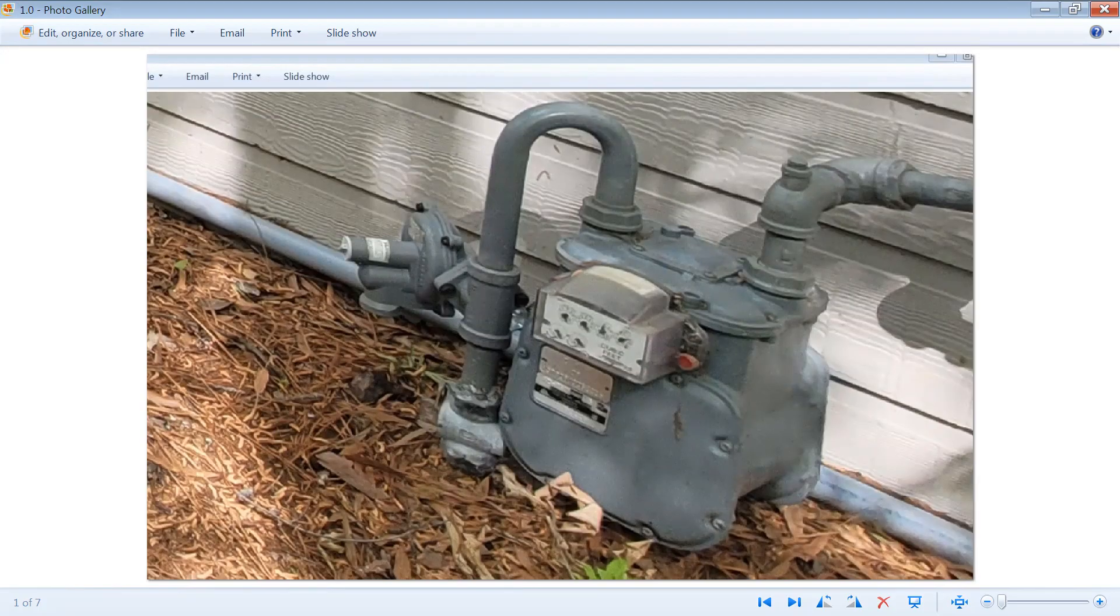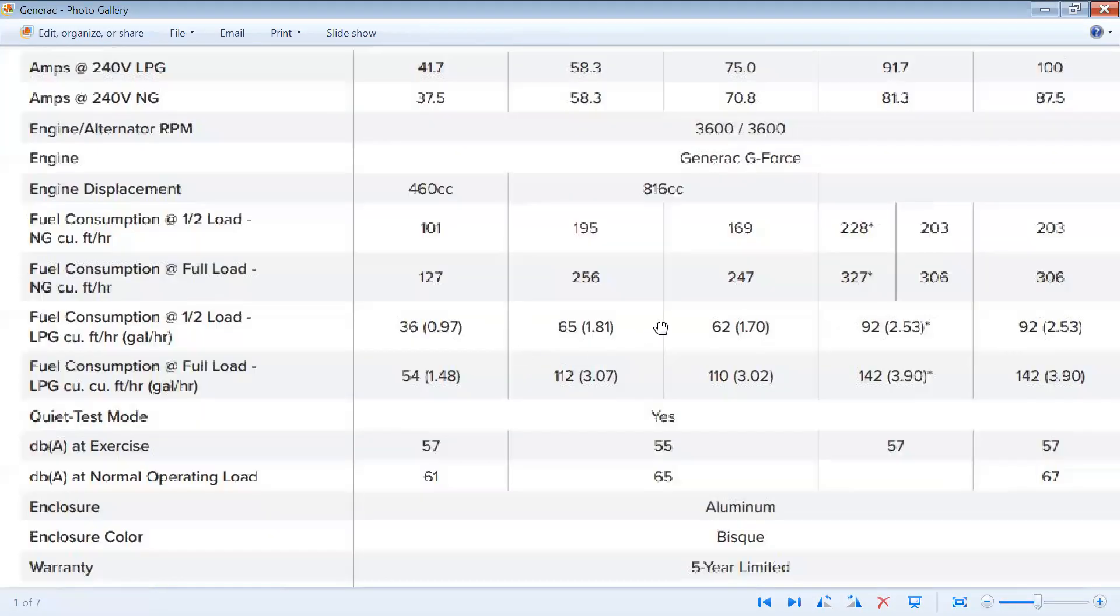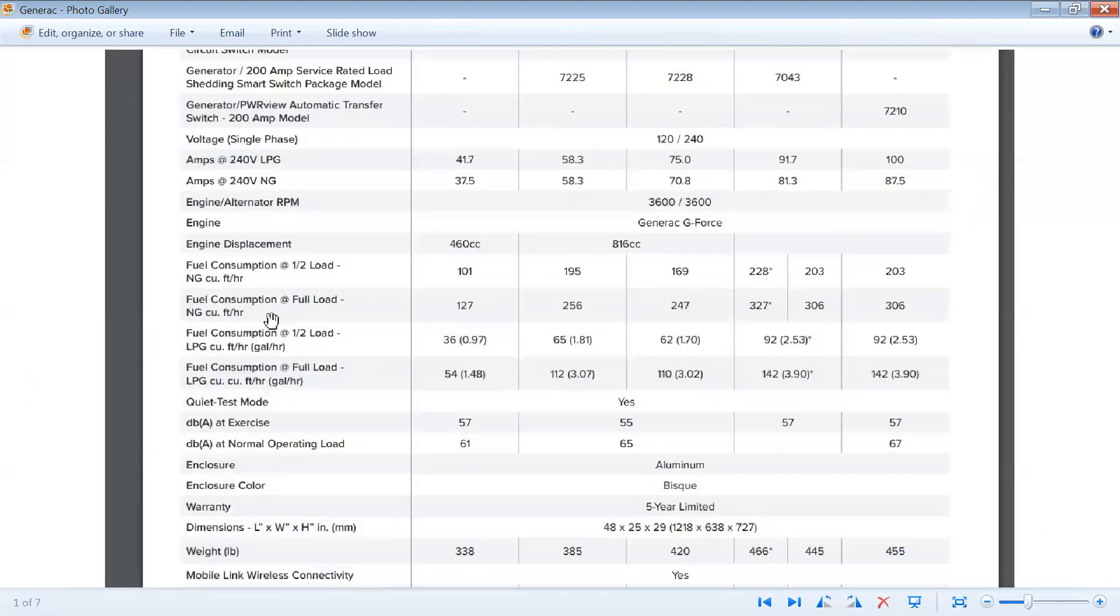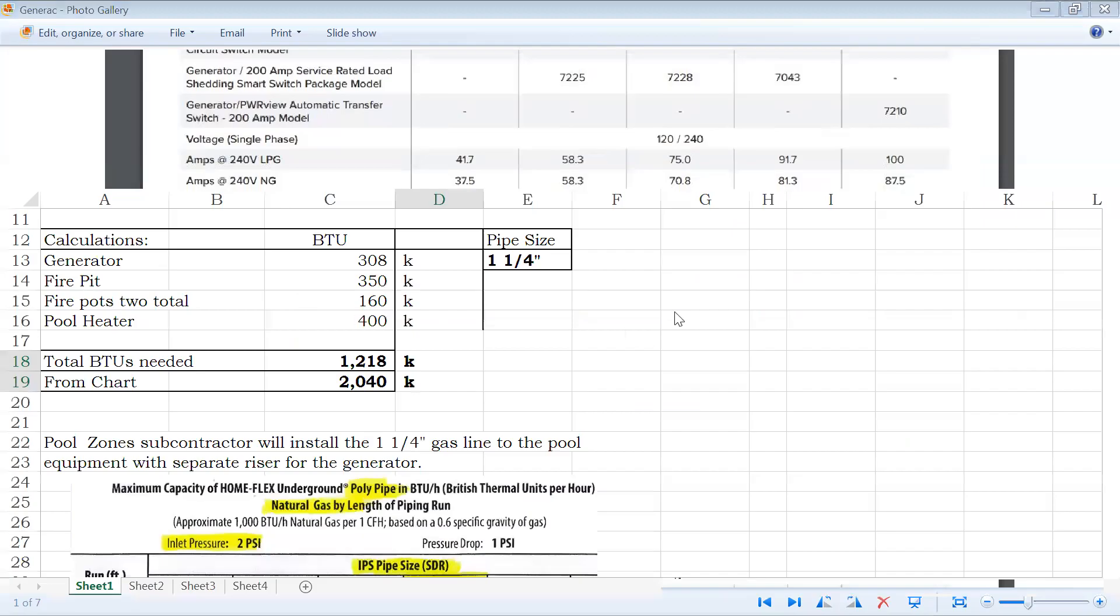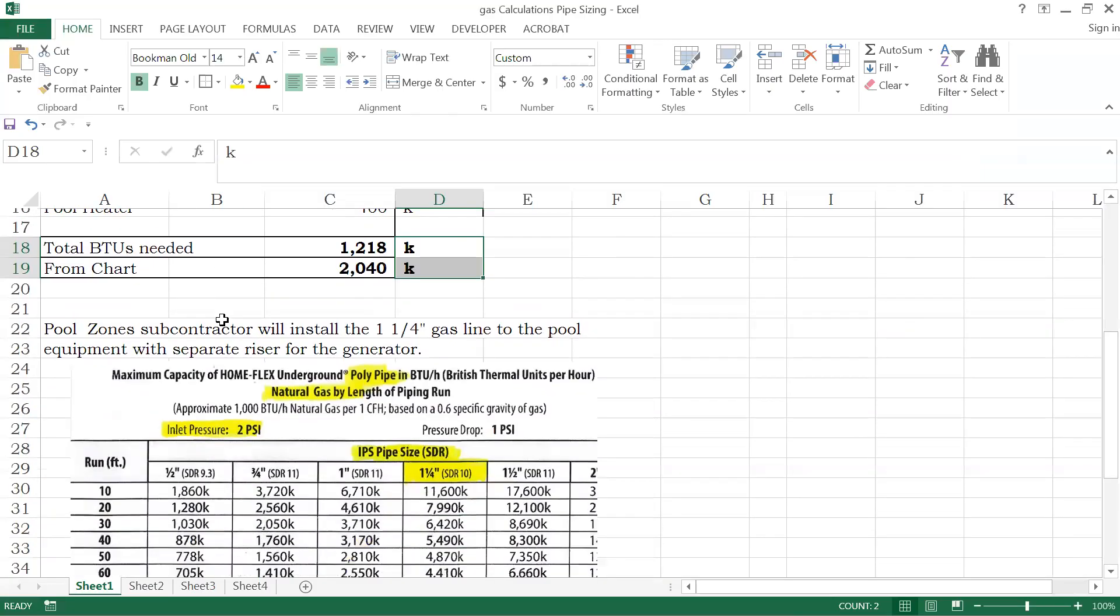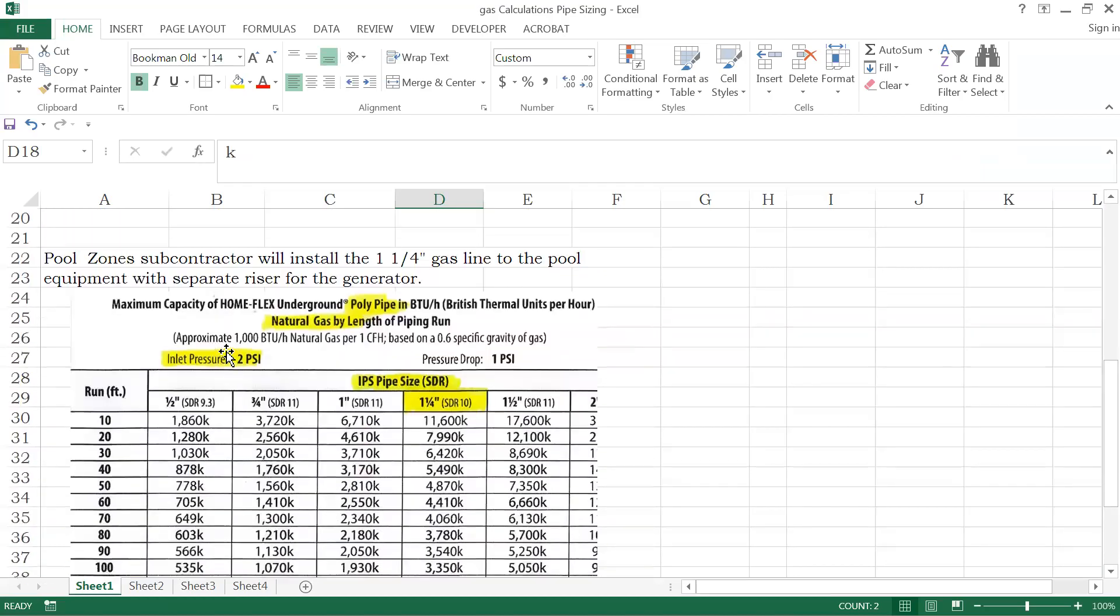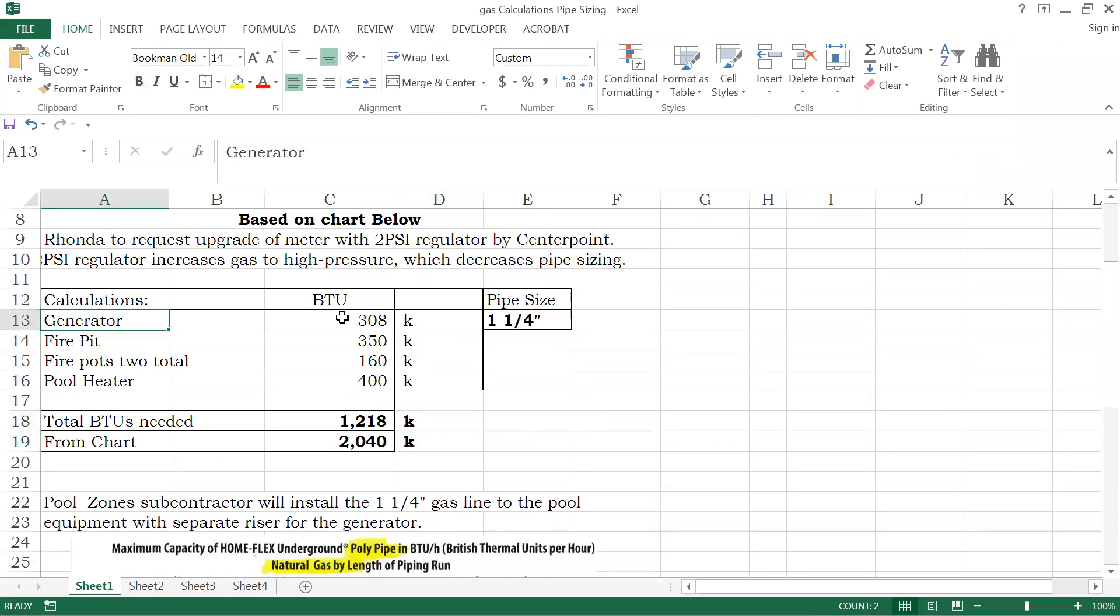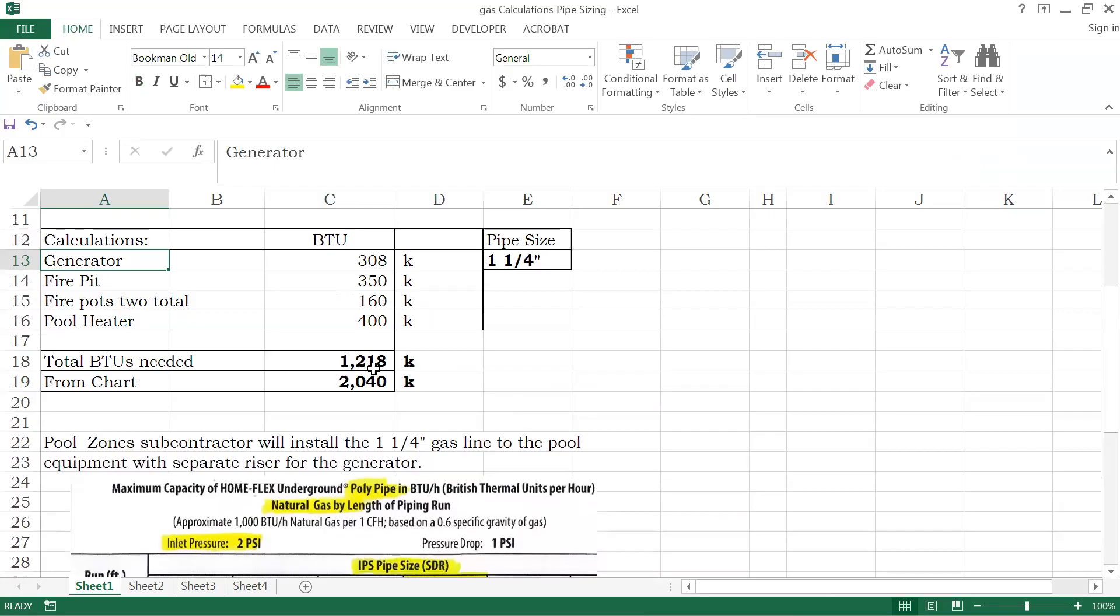Let's now look at the gas requirements for the generator. I'm working here on natural gas, I'm not interested in propane. The fuel consumption full load natural gas is 306k, which is 306,000 BTUs. I'm just going to call everything k because it's easier to do the numbers. Looking at my calculations, the first thing I'm going to do is look at what I need and go down and look at the chart. My calculations are the generator takes 308k, the fire pit 350, I'm giving an example of a job here, 160 for the two pots and 400 for the pool heater. So my total BTUs in thousands is actually 1,218.